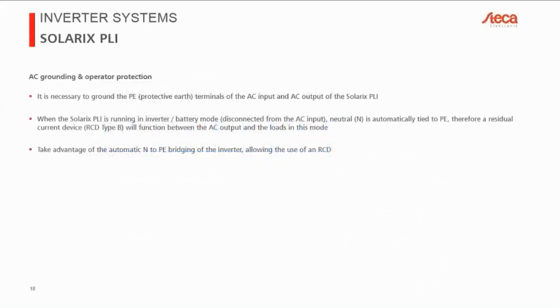Now to the AC grounding and operator protection. It's necessary to ground the SOLARIX PLI. By the way, it is not absolutely necessary to ground the SOLARIX PI. It is a protection class 2 device, so it's not absolutely necessary. But for protection of operators, you may be required to do so depending on your country to be able to run a residual current device. But for the functionality, it's not required. For the SOLARIX PLI, for safety reasons, we do need a ground connection.